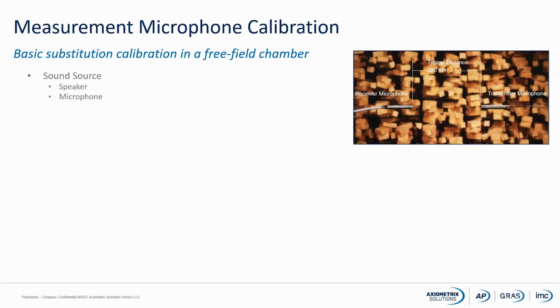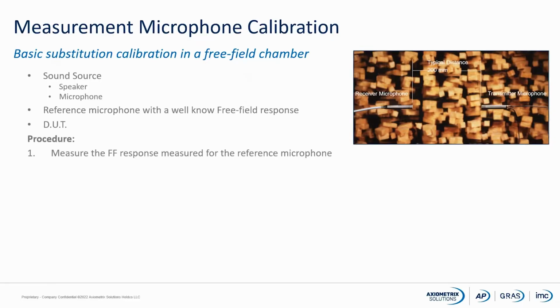Let's have a closer look, because in both cases we will need a sound source, and the sound source can either be a speaker or a microphone. We also need a reference microphone with a very well-known free field response. A reference microphone may be measured according to the primary standard, and of course we need the microphone under test. What are we going to do? First, we will measure the free field response of our reference microphone. Then we will measure the response for our microphone under test, and we have to ensure that we are placing the microphone in exactly the same position as we placed the reference microphone.